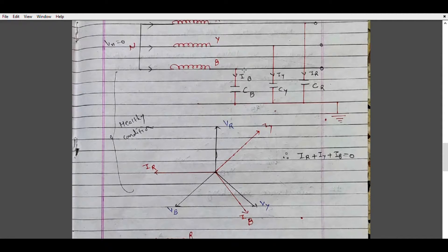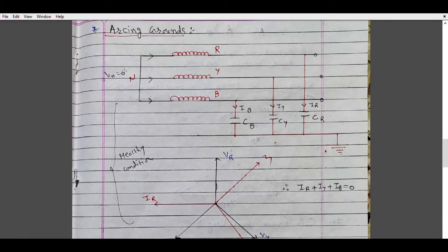The current will lead the voltage by 90 degrees, so we can say Ir leads voltage Vr by 90 degrees. Similarly, Iy and Ib lead Vy and Vb by 90 degrees. We are assuming this is a healthy condition, and that is why Ir + Iy + Ib = 0, and the voltage at the neutral will also be zero.